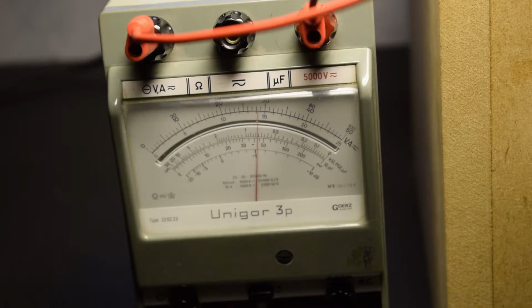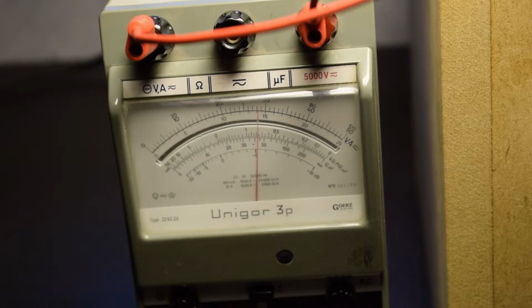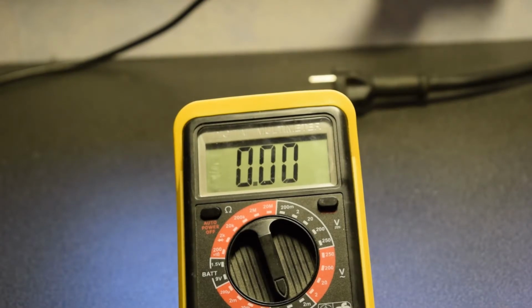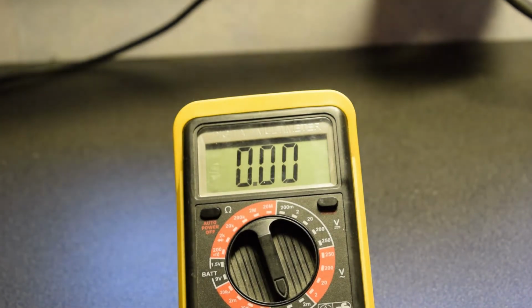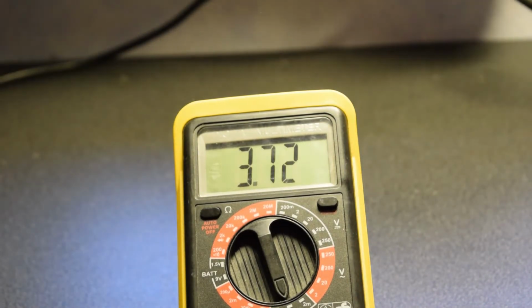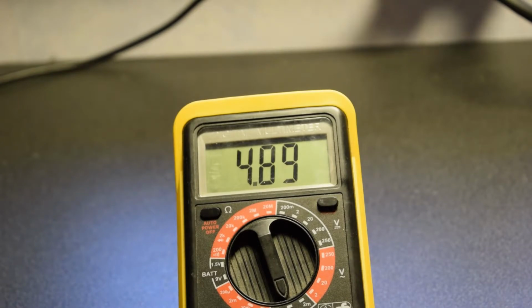So with the ballast connected, you're basically getting 75% of the full voltage. Now that we know the voltages, we can go and measure the current draw on the primary side, both unballasted and ballasted, with and without load. First, we're going to measure the current without the ballast and without any load. So let's plug it in, and we are getting about 4.89 amps. Well, 4.9 basically.